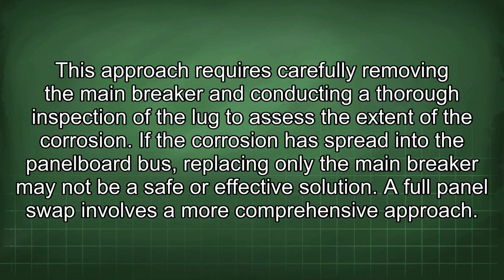This approach requires carefully removing the main breaker and conducting a thorough inspection of the lug to assess the extent of the corrosion. If the corrosion has spread into the panel board bus, replacing only the main breaker may not be a safe or effective solution.